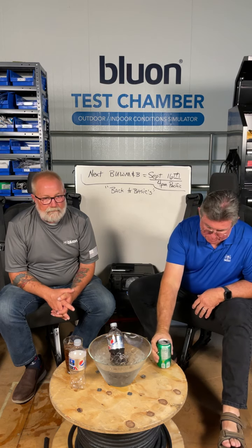Yes. And if you're still using R22 on an R22 machine, we realize it's really expensive, but if you are using R22, everything you read tells you do not charge a running unit with liquid. If you do pull it off as a vapor, your tank pressure is going to go down, and then you're going to get to a point where you can't pull any more refrigerant out of the tank. Unless you want to get really affectionate. So yeah, you can sit there and hug it.